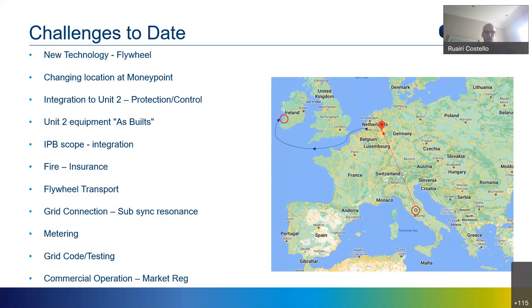And then on the grid side, there are a few challenges because it's new technology again. There was a potential risk of subsynchronous resonance, a capacitor on the transmission system network causing an impact and possible vibrations on the unit, which we ruled out in conjunction with EirGrid, the TSO. Metering is new for synchronous condensers, and you get errors at large megavars, so we've had to implement a backup meter to check the EirGrid metering. The grid code is written for thermal generators, and then there's the commercial operation piece and how this unit will run in the market. So EirGrid are bringing out a new document for synchronous condensers specifically, which will cover a lot of these issues.